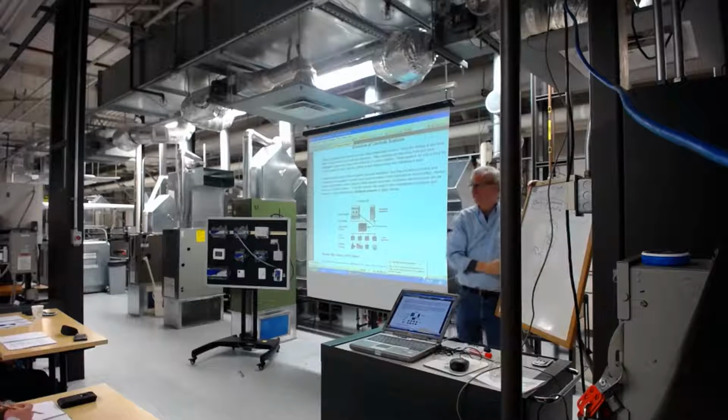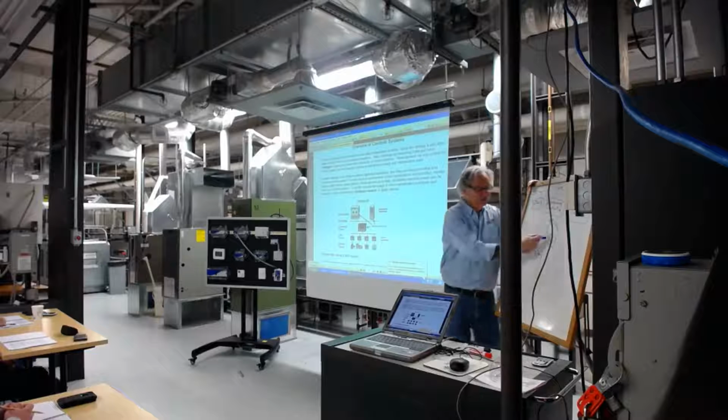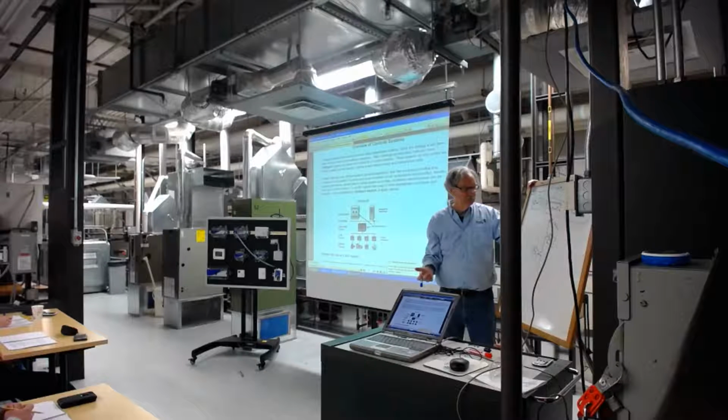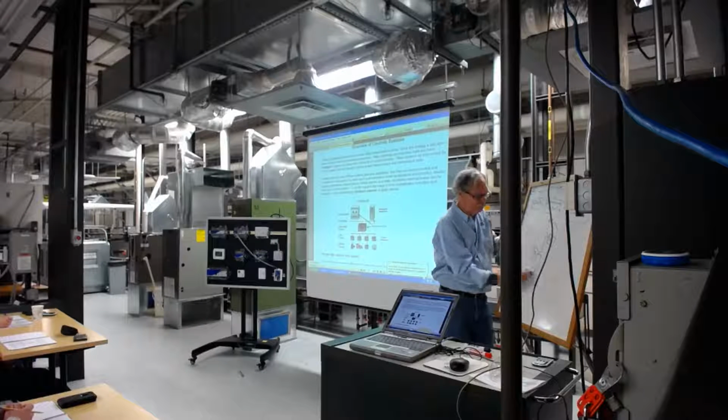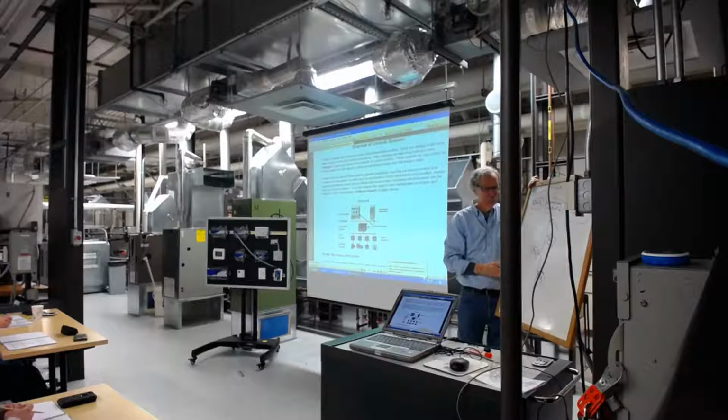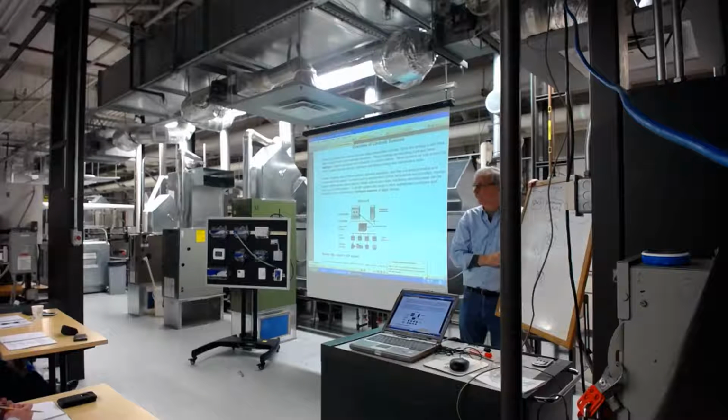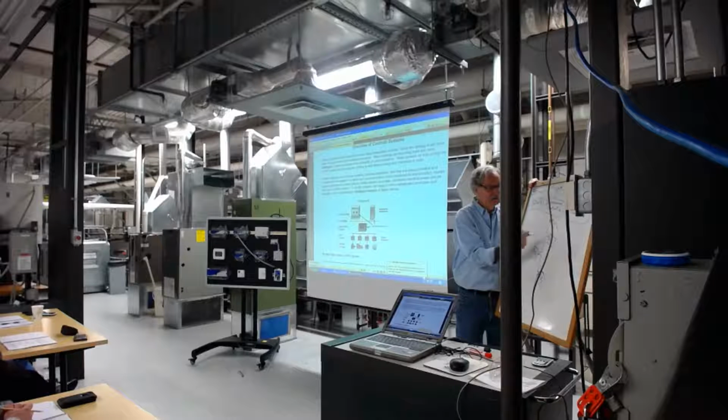So you've got these. This is where the action is. When you have a digital controller, it's programmed by the vendor to do a function. This could be an air handling unit. This could be a central plant. You could have VAV boxes, and so on and so on. So they're programmed, they're standalone. So even if you lose a field bus, you're not losing your building. You'll still continue to control your air handlers, your pumps, your boilers, whatever it is that's going on. Okay. So that download program is proprietary.